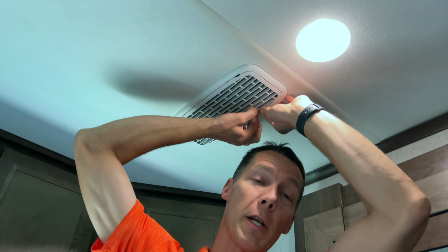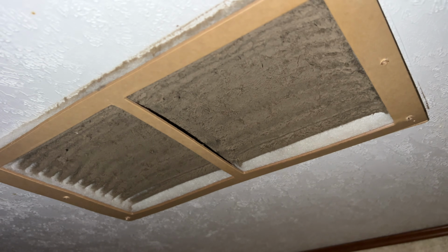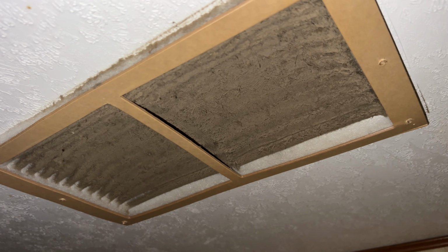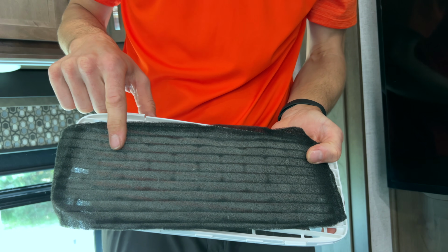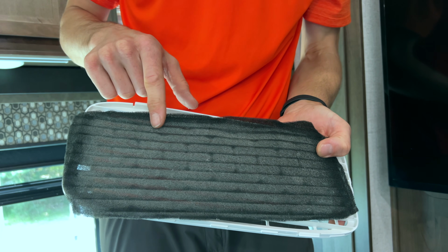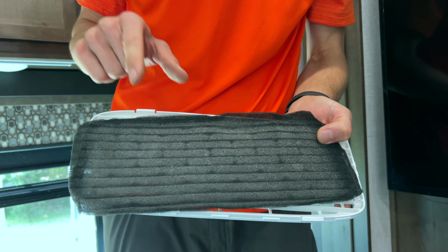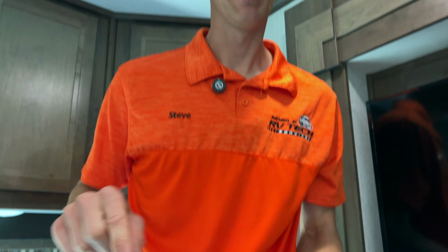Now these ones will be pretty clean, but I'll put some pictures on the screen of customers' ones that were very, very dirty. Dust, debris on these filters can block airflow into the AC unit, which will definitely slow the airflow out of the unit and not cool very well. Sometimes it's a simple cleaning. Other times it could be some collapsed ductwork or you have some issues inside of there.